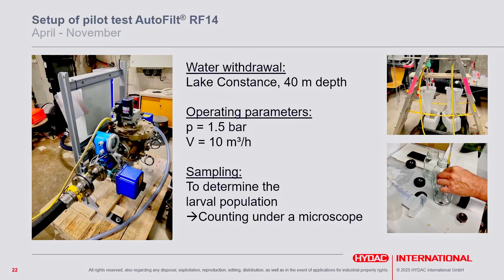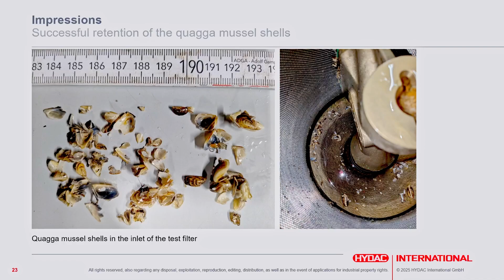Another important impression you can see on the next slide. Over several weeks of operation, we opened our filter, and what we found was very interesting. Although the university said we have clean water, we take this water for drinking purposes and so on, we found a lot of mussel shells, up to 2, 3, 4 centimeters sometimes. And this leads us to the opinion that a cascade is needed. It is really a 2-stage problem. We cannot put only the fine filter in there, because these big particles are challenging for our fine filter. So both filters are important. Coarse filter for the shells, fine filter for the larvae.